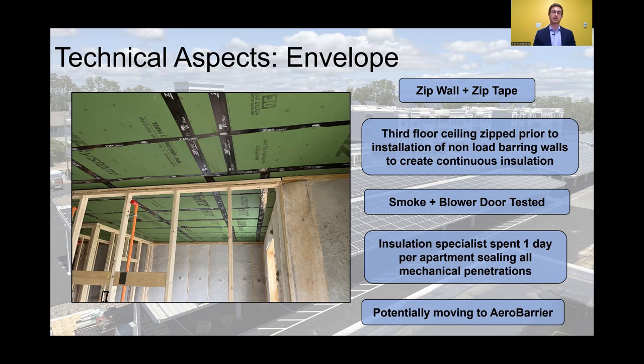Then they had an insulation specialist spend one day per apartment sealing all the mechanical penetrations between apartments. So that way your apartments are completely compartmentalized, so I can have my temperature settings on different than yours, and our air is not going to mix, causing inefficiencies. Going forward, they're thinking about moving to Aeroseal. Aeroseal is commonly used within ducting to seal penetrations to the air ducts, but it's being used more and more within buildings that are trying to achieve really low air exchange rates. Essentially, you pressurize the building and release this aerosol, and it sticks together and seals up around small penetrations in the envelope.